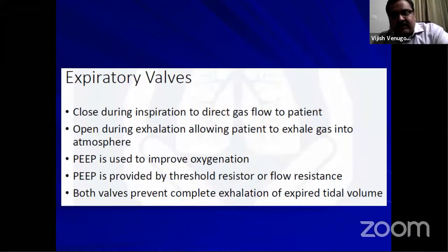We have expiratory valves, which are at the outlet. This closes during inspiration to direct gas flow to the patient, and it opens during exhalation, allowing the patient to exhale gas into the atmosphere. So this is the one which applies PEEP. There are 3 different types of expiratory valves in our ventilators.